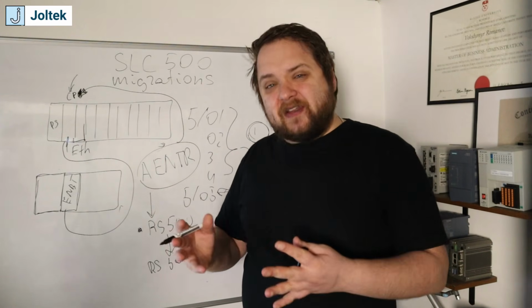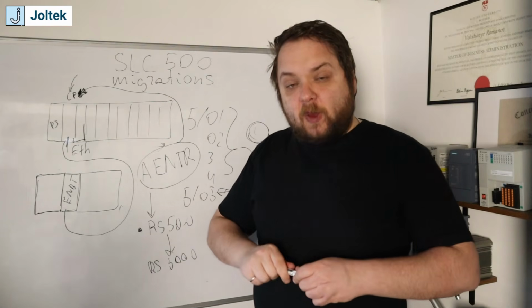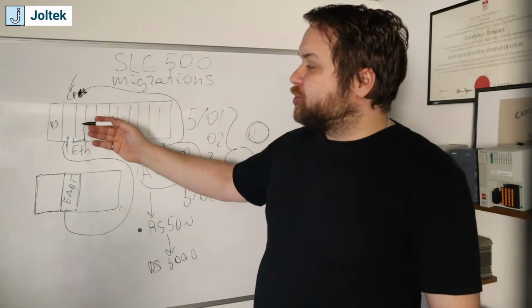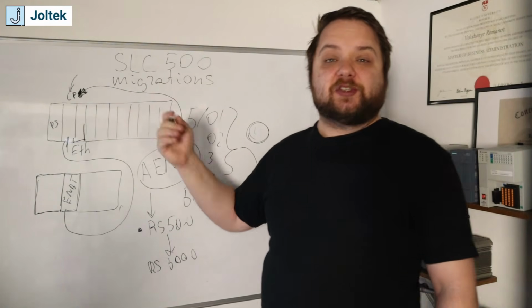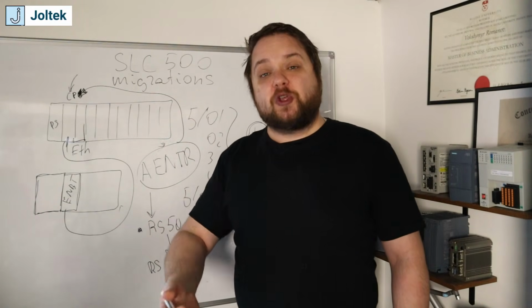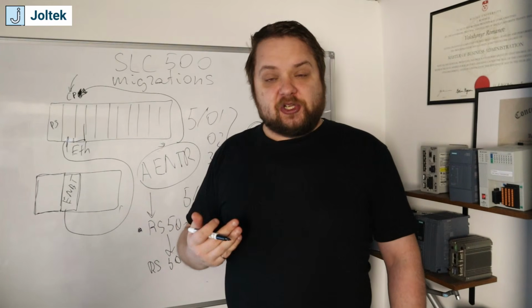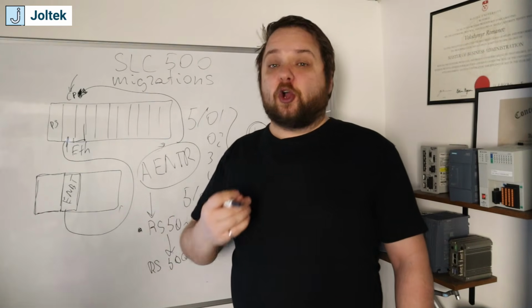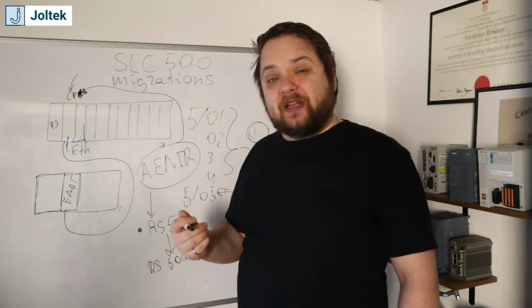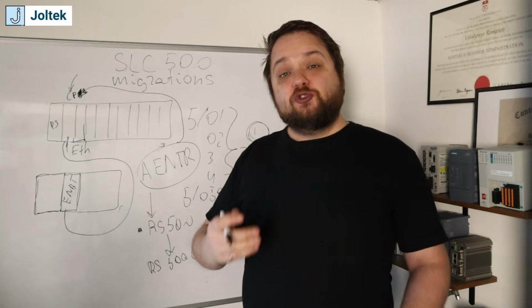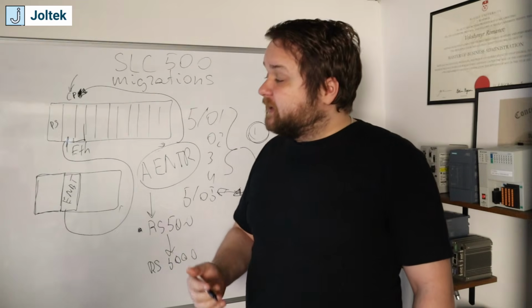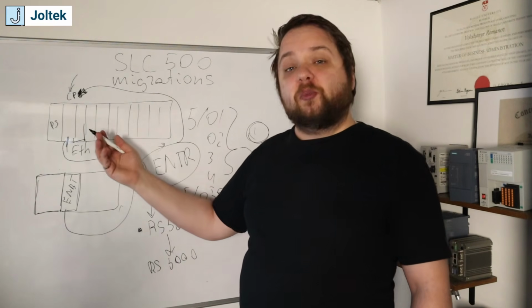So again, the caveats here are multiple, but what I usually recommend is you extract the program that you have inside of your PLC, you convert it to the RSLogix or Studio 5000 equivalent, you then add all of the cards into an offline program of this PLC to ensure that they all communicate and are connecting as expected. You then run a small proof of concept.